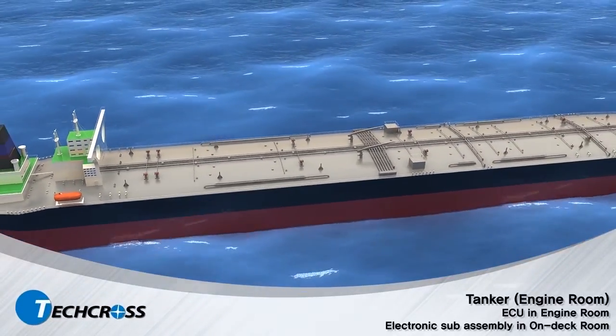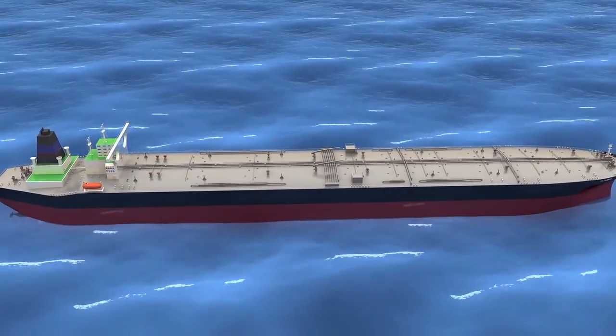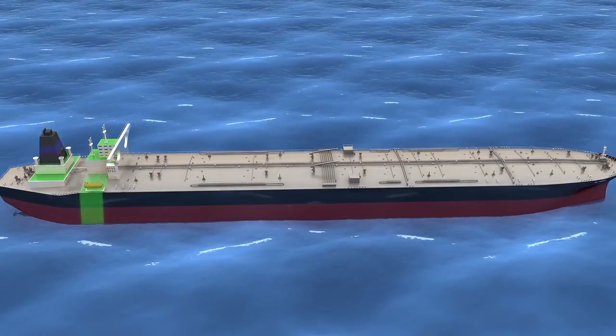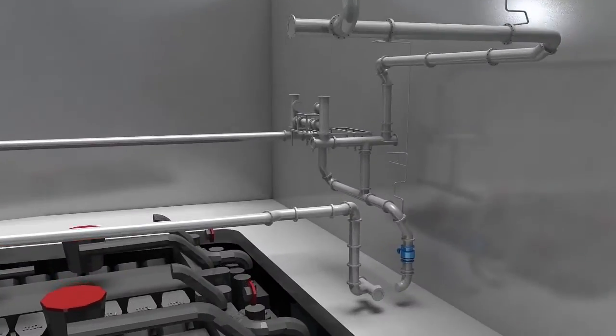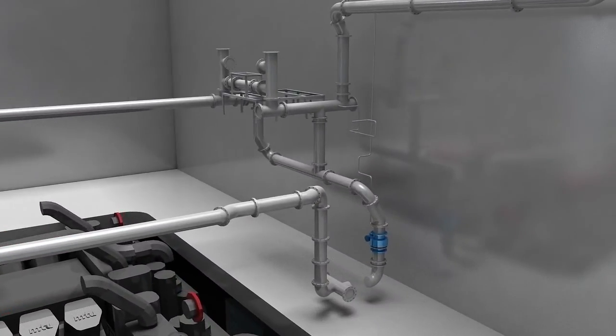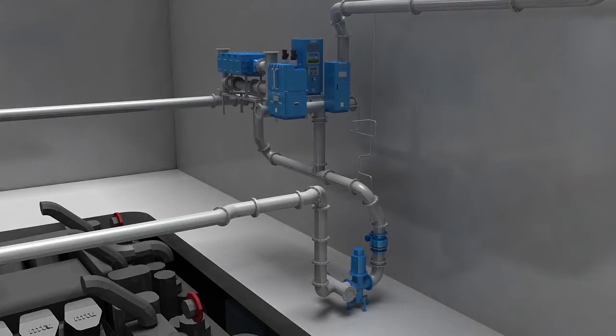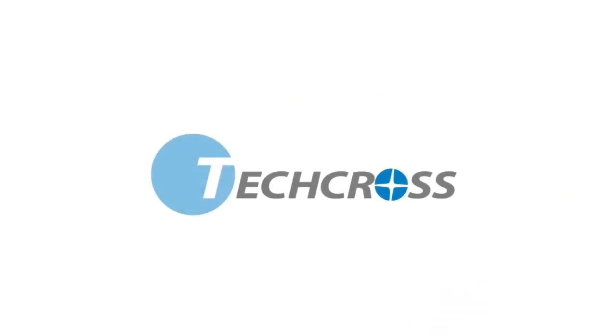Some tankers which have no pump room but submerged ballast pump can install the non-explosive ECU in the engine room with an additional ballast pump. This design is possible because ECS does not require re-treatment at discharging. Even though the additional pump will need to be added in the engine room, this is a much more economical solution.